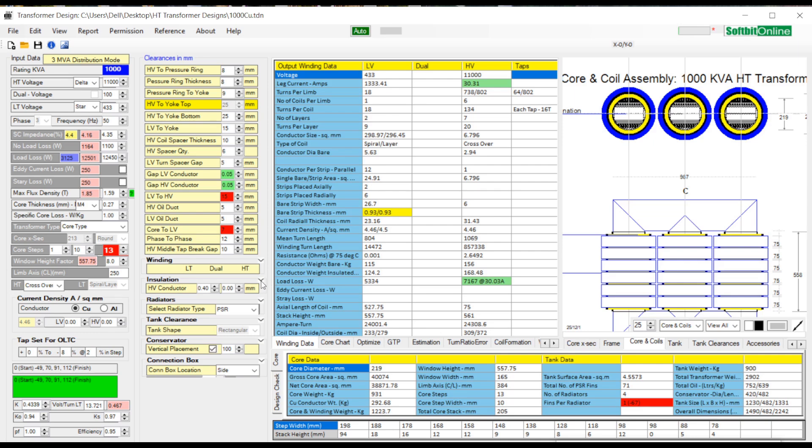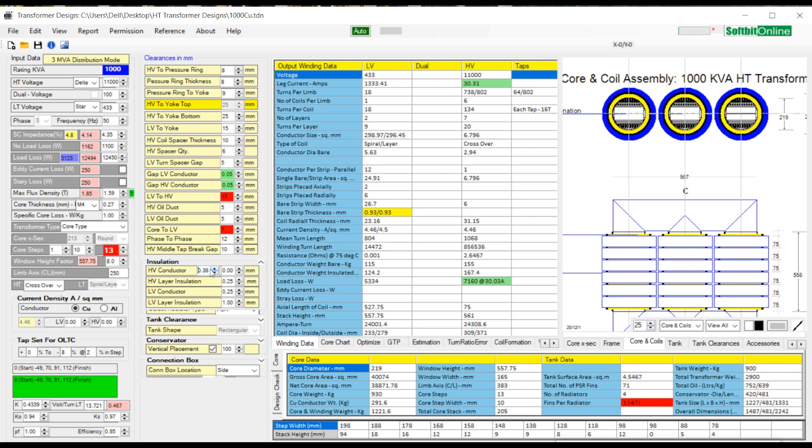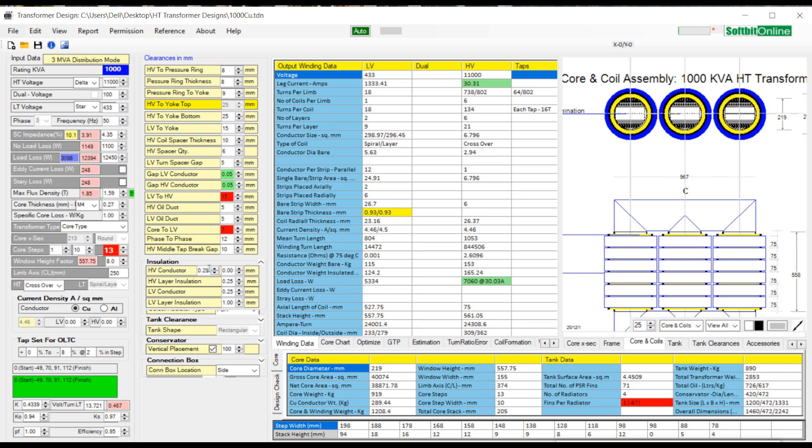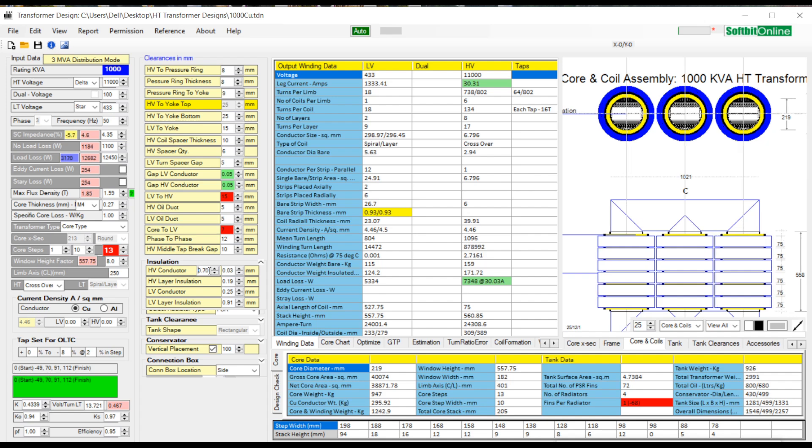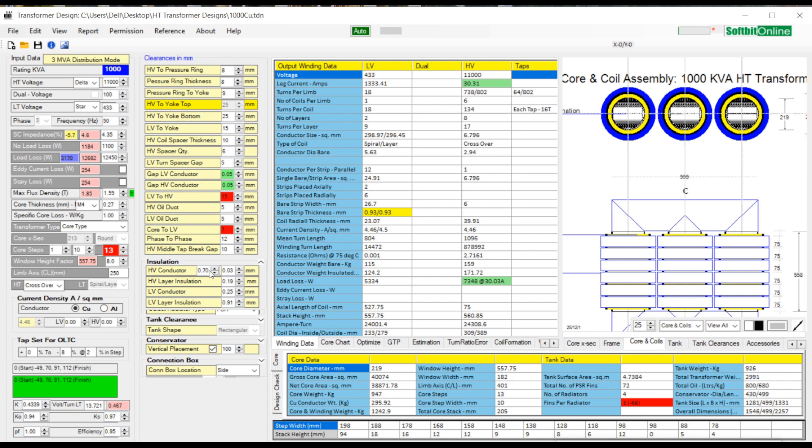Next we expand the insulation tab. Under this tab we can change the HV and LV conductor insulation. You can also change the layer insulation of HV and LV windings. See the dynamic effects in drawings if you change the HV conductor insulation. You have to be very precise and alert while changing the conductor insulation. As you change the conductor insulation of HV winding conductor, its coil diameter changes and this dimensional change directly affects the percentage impedance of the transformer.